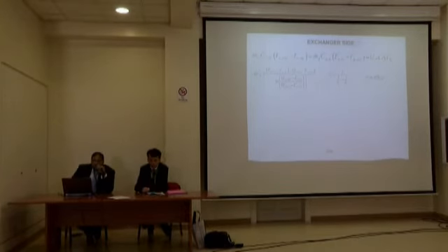But at the same time, if we look from an energy point of view, we have done another study where water at rest may be more efficient than water flow, which is unobvious. In heat transfer? Yes. Now, here it's important to say that the system also will depend on the capacity of the refrigerant in the HVAC system. So if we have a 1 ton refrigerant, it's not the same as, for example, 10 ton refrigerant. So the temperature of the condenser will depend on the water temperature and the quantity of water. Yes. Of course.